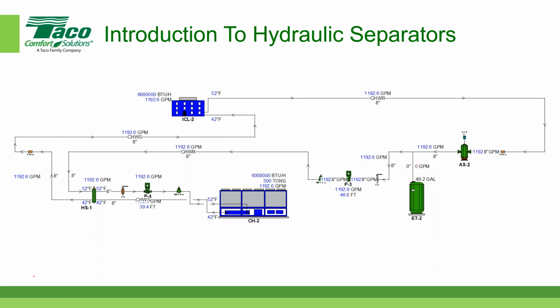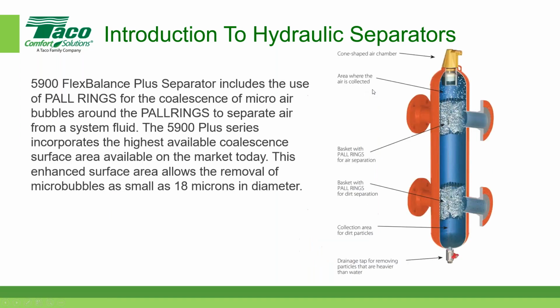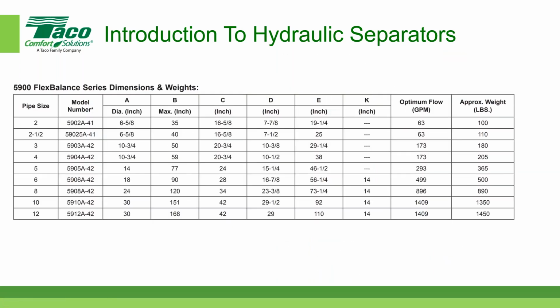If you'll notice, we have 1,200 gallons per minute in this system. That's the maximum for the primary and the secondary side. And it looks like the pipe size is 8 inches in this case. All right, so let's look at the sizing chart and see what the 1,200 gallons per minute is going to come down to. So if we first said, well, look, we have an 8-inch pipe, so there's 8-inch pipe right there. Is that the proper size unit that we should put into this system?